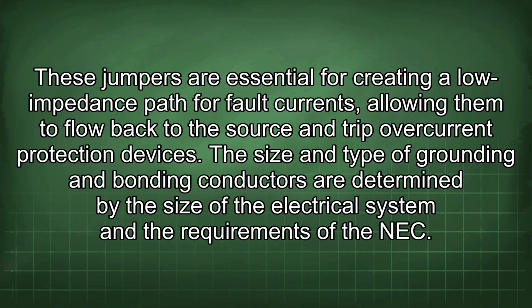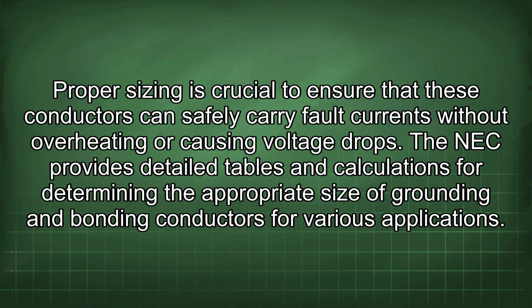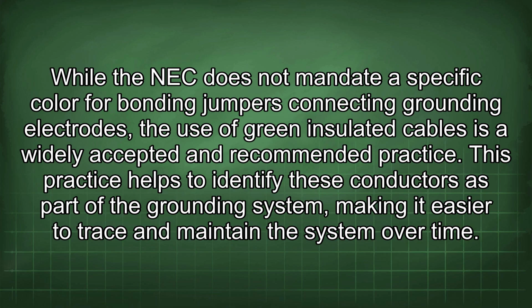The size and type of grounding and bonding conductors are determined by the size of the electrical system and the requirements of the NEC. Proper sizing is crucial to ensure that these conductors can safely carry fault currents without overheating or causing voltage drops. The NEC provides detailed tables and calculations for determining the appropriate size of grounding and bonding conductors for various applications. While the NEC does not mandate a specific color for bonding jumpers connecting grounding electrodes, the use of green insulated cables is a widely accepted and recommended practice.